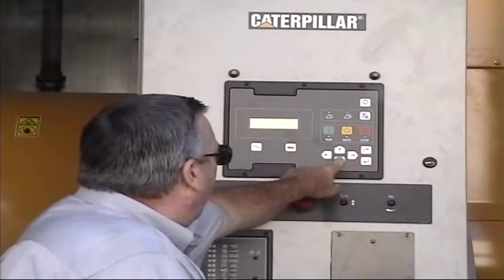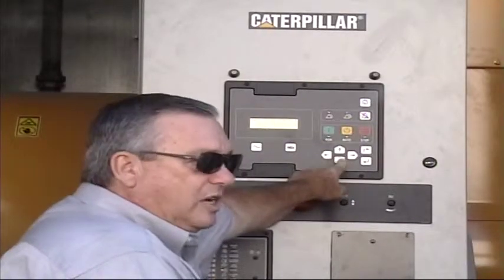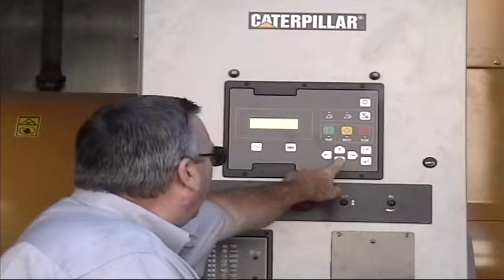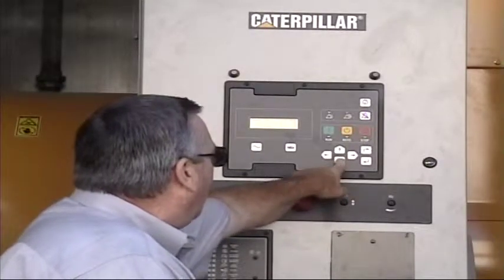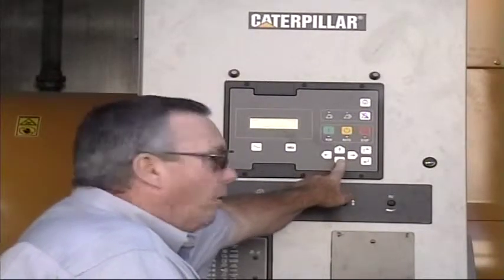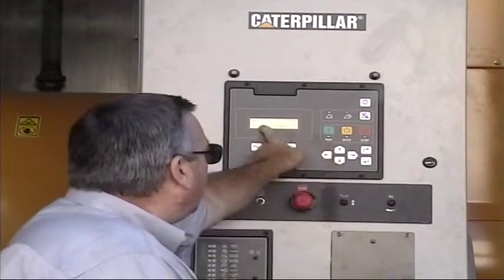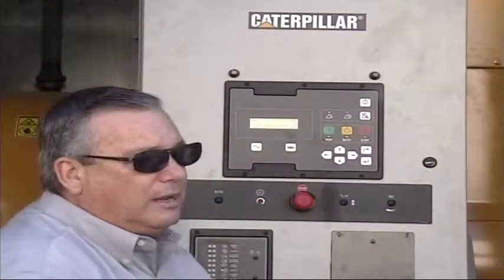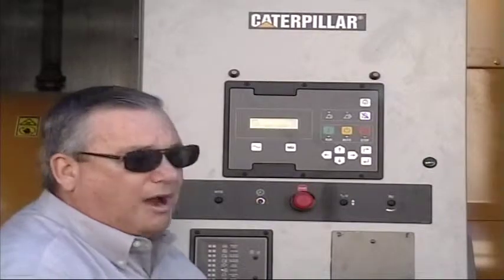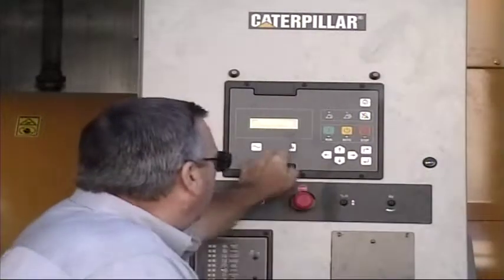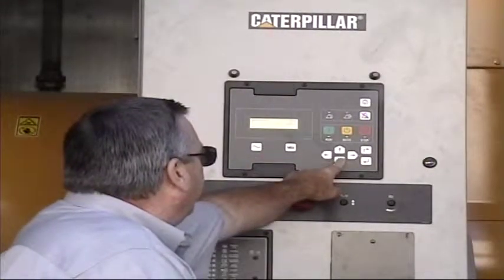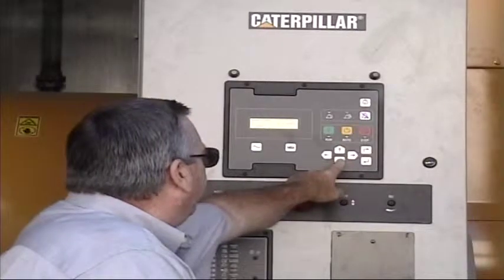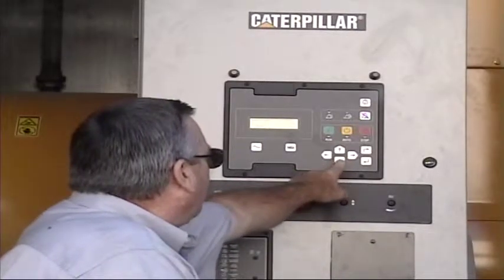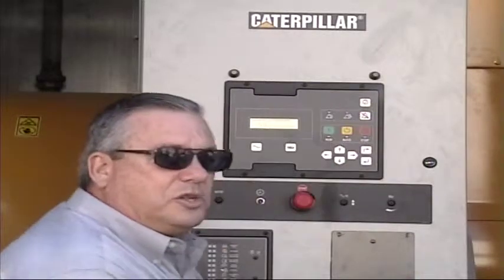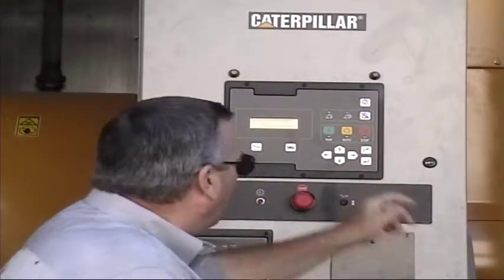Also, if you scroll down, you can get leg-to-leg voltage, amps, total kW, k-vars, kilowatt hours. That'll total your kilowatt hours, and it'll also total your engine hours, and those are non-resettable. And average leg-to-leg, excitation voltage, and once you go too far it'll tell you no more information available.